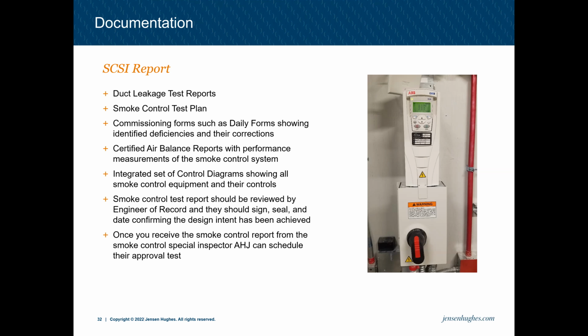During smoke control special inspection, we create daily forms or daily logs that identify usually what I test. So it's clear that, hey, we tested these things two weeks ago, they worked, and hopefully we don't need to retest. Conversely, if we tested them two weeks ago and they don't work this time, it's good just to document that to see what happens. Those daily logs will also show deficiencies, and I think that's a great thing, rather than just saying them to the CM or the GC who's walking with us. They detail what needs to be done so that can be passed around between the subcontractors and maybe the engineers of record.